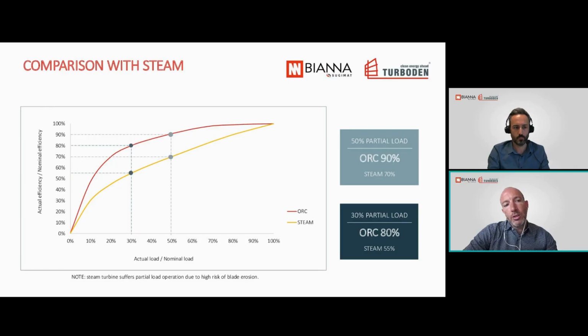Steam systems, on the other hand, don't handle off-design conditions nearly as well. I would say their efficiency tends to drop off much more sharply when they are not running at full load. And so flexibility is a big advantage in favor of ORC and makes ORC turbogenerators, I would say, a great fit for applications where the thermal input isn't always constant. And I think that's the case for waste to energy applications, where you may have fuels with a calorific value not really stable. So yeah, I think that's about it. Maybe we can now jump into a real case with Alex.